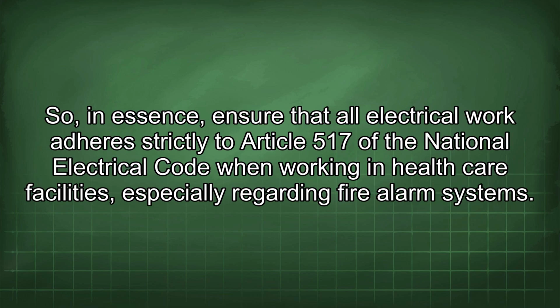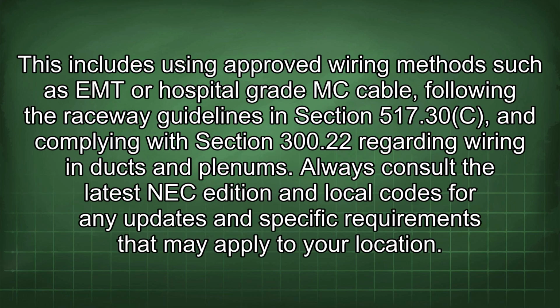So, in essence, ensure that all electrical work adheres strictly to Article 517 of the National Electrical Code when working in healthcare facilities, especially regarding fire alarm systems. This includes using approved wiring methods such as EMT or hospital-grade MC cable, following the raceway guidelines in Section 517.30(C), and complying with Section 300.22 regarding wiring in ducts and plenums.